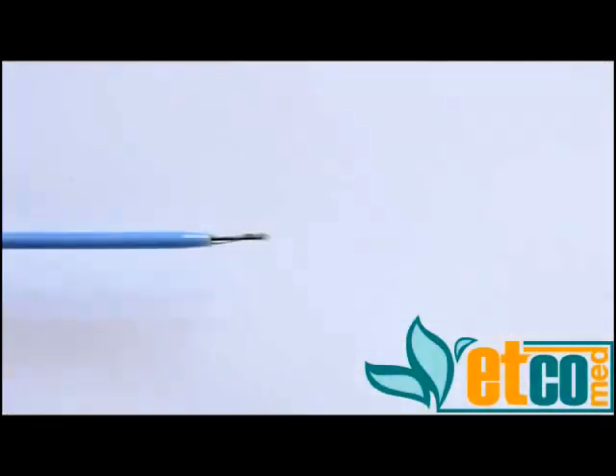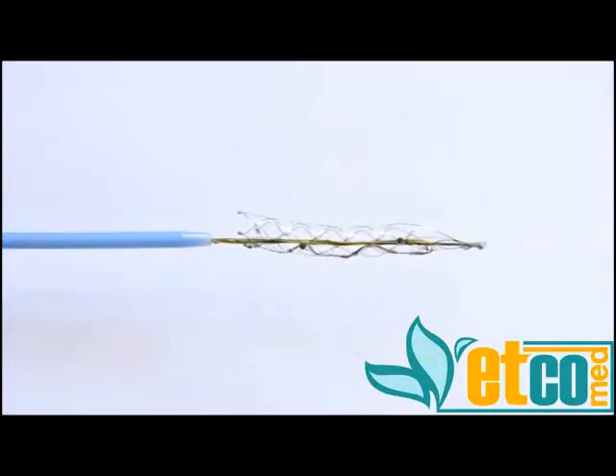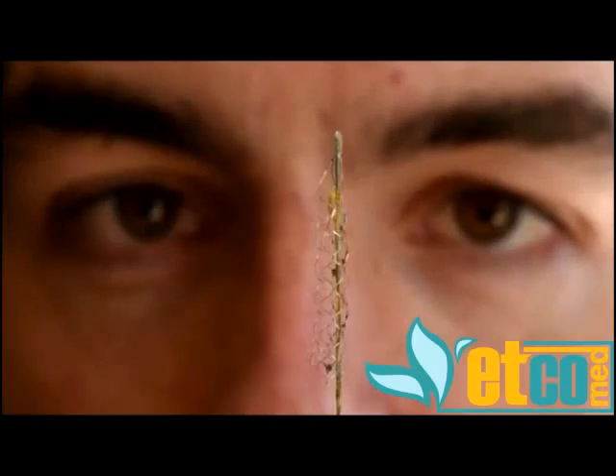The device is made out of nitinol, a nickel-titanium composite that enables it greater resilience when being flexed and compressed over other more commonly used materials, which allows us to deploy it through a very small catheter and expand it to a larger size when in the blood vessel region of interest.